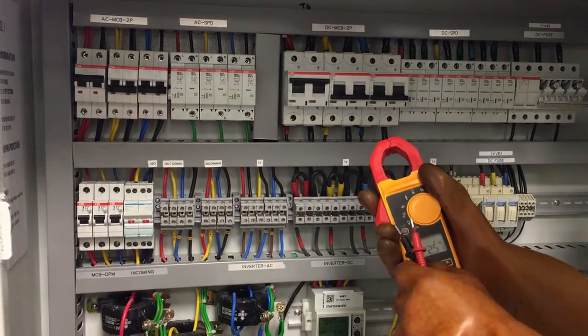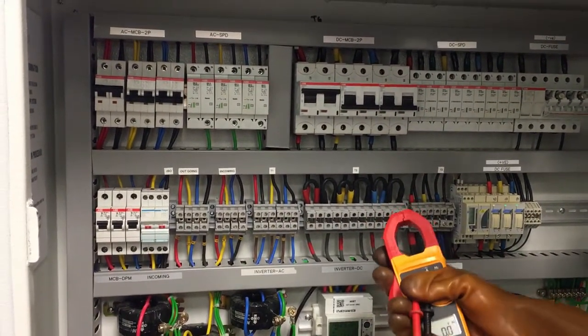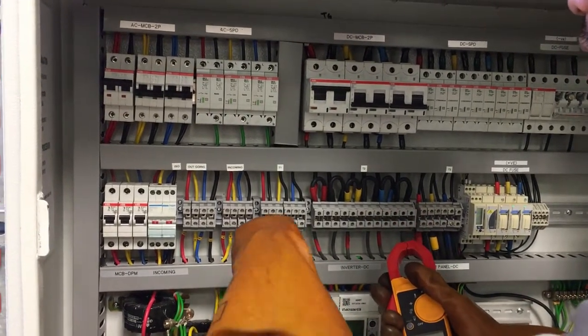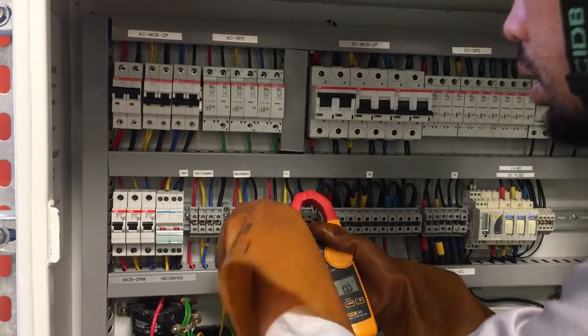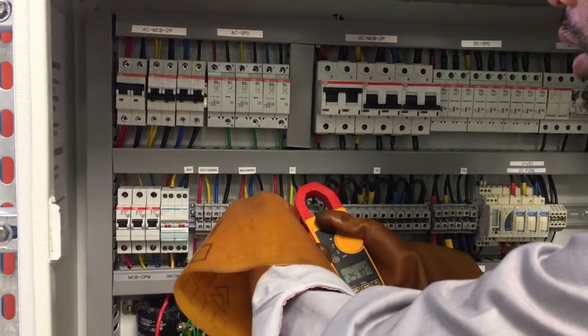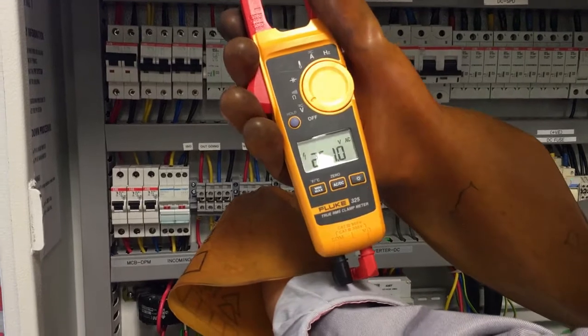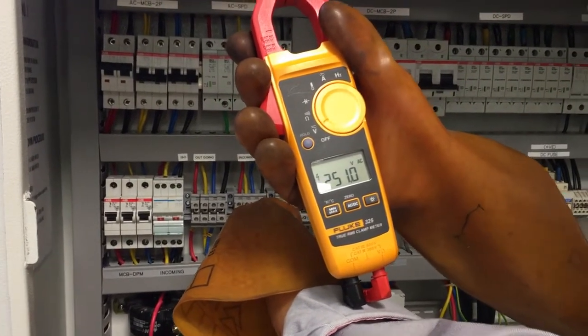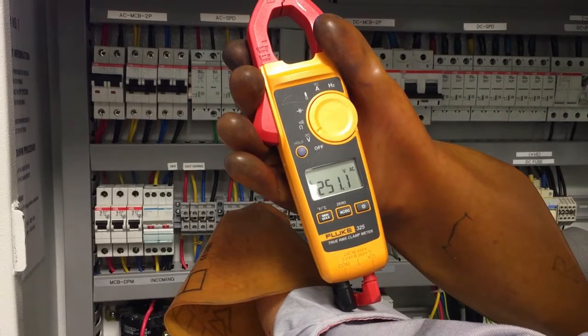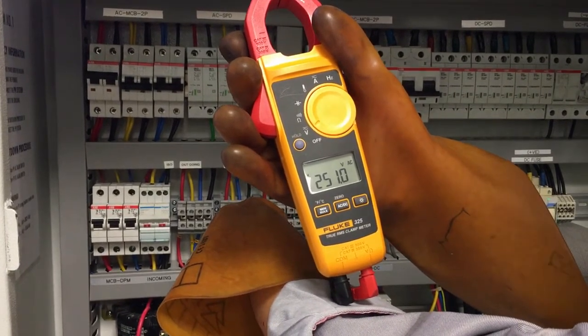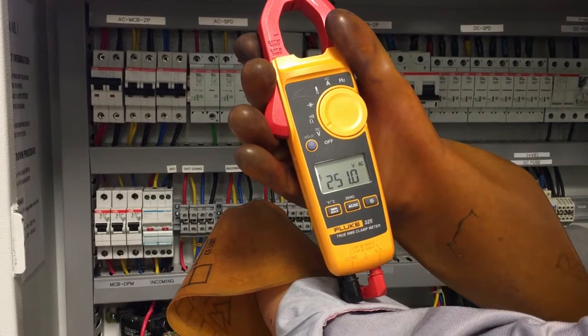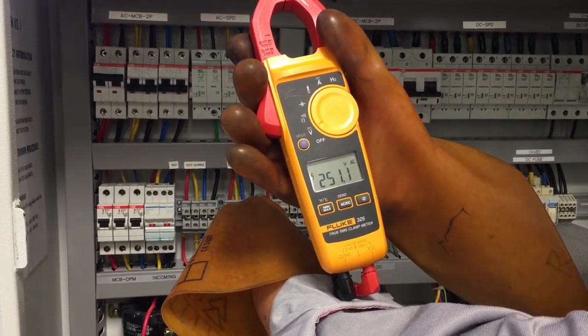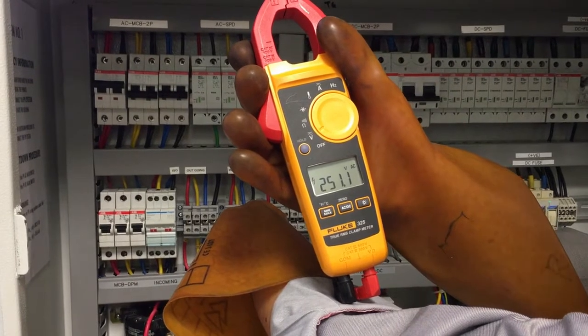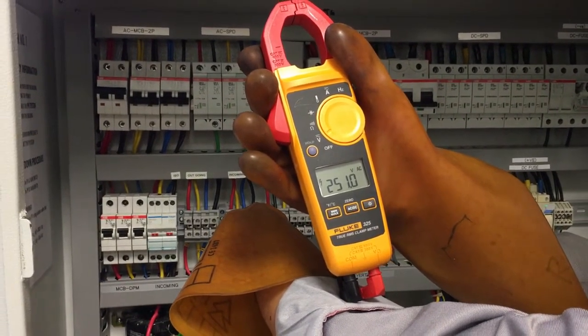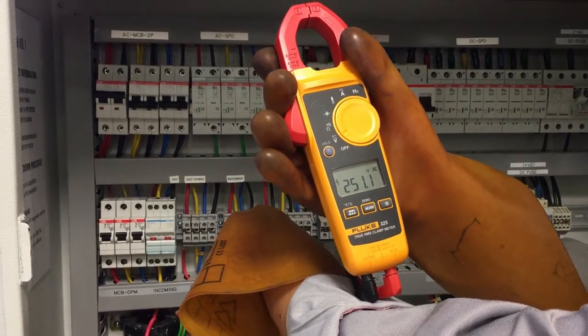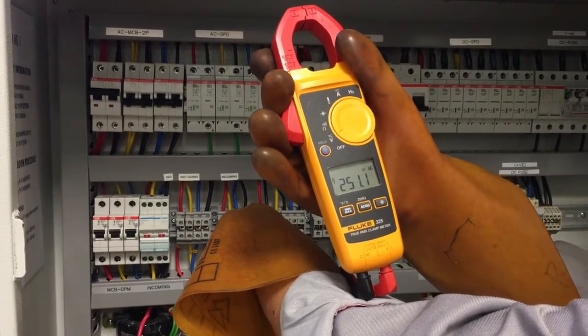Okay, now AC voltage, I measure at the output of the inverter. The value is 251 volt AC. Okay, our standard single phase is 240 or 230, right? So in U10, because we are close to the substation, so our voltage is a bit higher to compensate for the voltage drop when the cable goes out from our transformer to nearby areas. So it's a bit higher, but still within normal range.